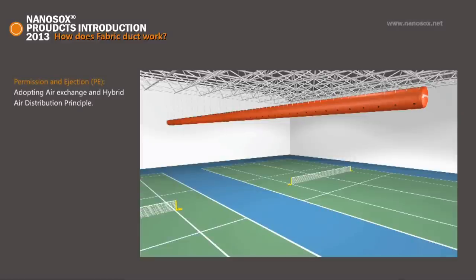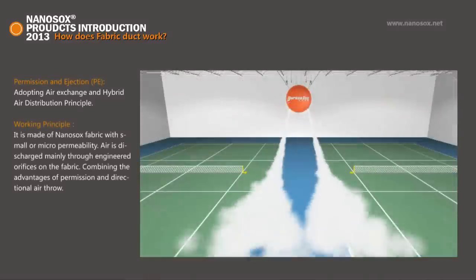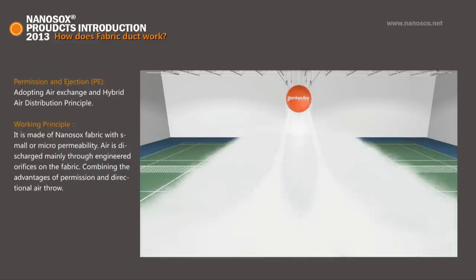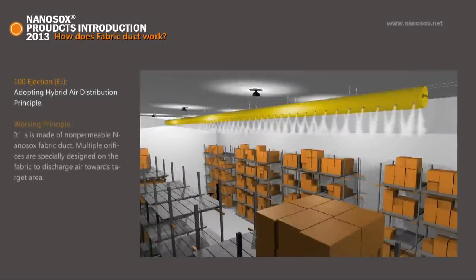Permeation and Ejection PE: It is made of Nanosox fabric with small or micro permeability. Air is discharged mainly through engineered orifices on the fabric. Combining the advantage of permeation and directional air throw, it is suitable for high ceiling, condensation-free cooling and heating systems.